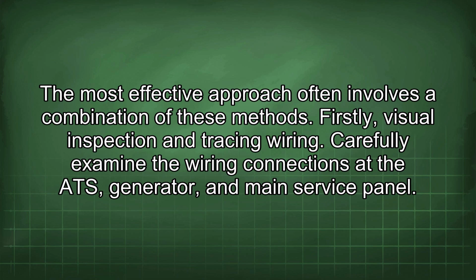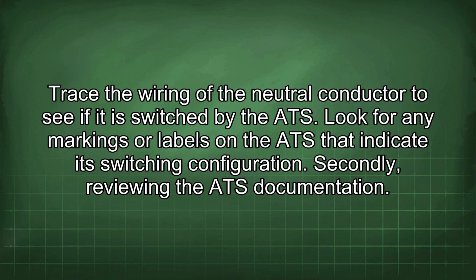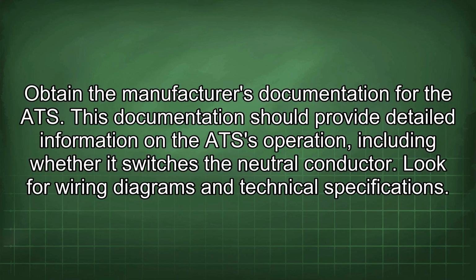Firstly, visual inspection and tracing wiring. Carefully examine the wiring connections at the ATS, generator, and main service panel. Trace the wiring of the neutral conductor to see if it is switched by the ATS. Look for any markings or labels on the ATS that indicate its switching configuration. Secondly, reviewing the ATS documentation. Obtain the manufacturer's documentation for the ATS. This documentation should provide detailed information on the ATS operation, including whether it switches the neutral conductor. Look for wiring diagrams and technical specifications.